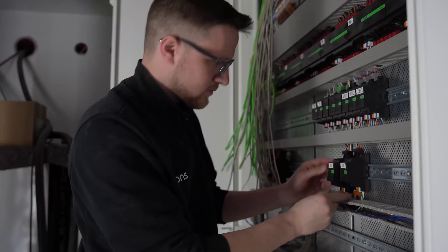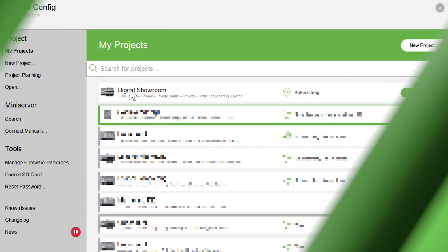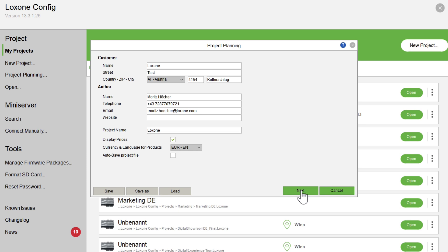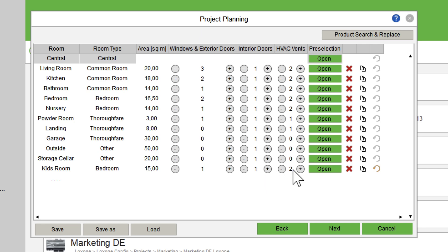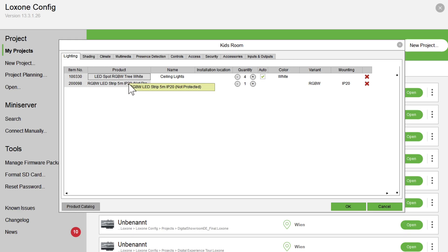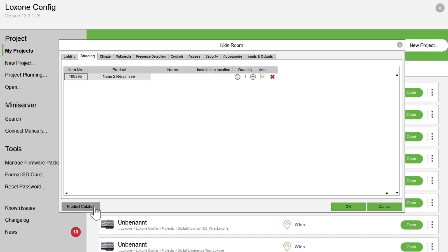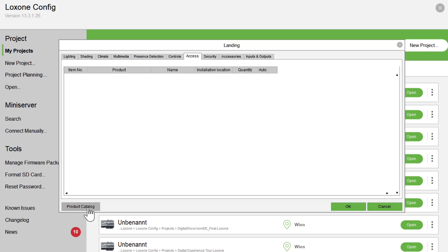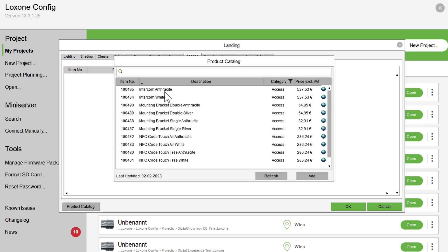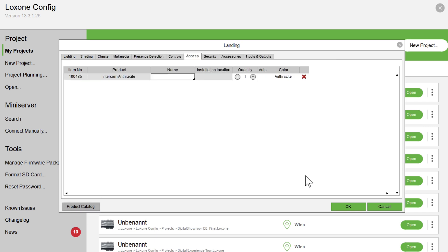The last step is planning the components and setting up the control cabinet. This step is extremely easy thanks to the Loxone Config and the project planning tool. In the project planning tool we simply create the required rooms, enter their parameters, and then enter the components we have designed into the floor plan. We need all products related to lighting, shading, touches, presence detectors, window contacts, and everything to be in the right order. The advantage is that we don't have to worry about which components we need in the control cabinet, because the project planning tool inserts the necessary extensions exactly after the selected components.